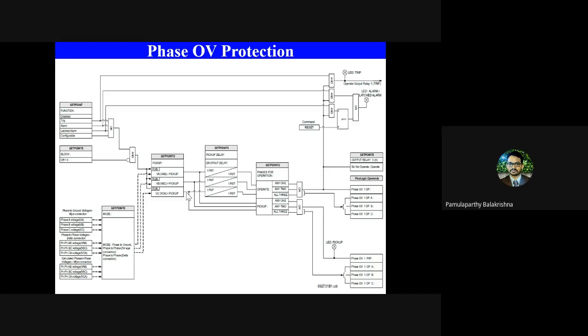Okay, so the insulation of all the equipment is designed for certain voltage levels. So an overvoltage condition creates stress on the insulation of the various equipment and can even damage it. That's why you can take immediate action: once the voltage crosses pickup, you can inform the operator immediately that the phase overvoltage element has picked up. Okay, so you can see PKP means it has picked up but not executed.